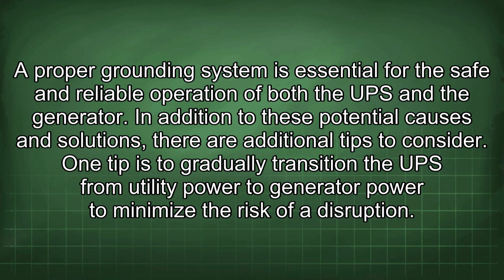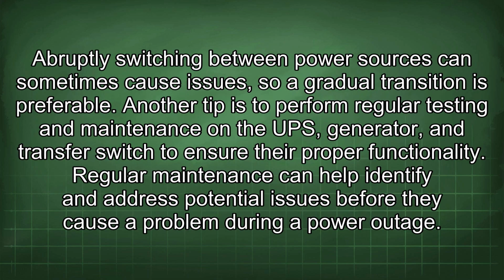In addition to these potential causes and solutions, there are additional tips to consider. One tip is to gradually transition the UPS from utility power to generator power to minimize the risk of a disruption. Abruptly switching between power sources can sometimes cause issues, so a gradual transition is preferable. Another tip is to perform regular testing and maintenance on the UPS, generator, and transfer switch to ensure their proper functionality. Regular maintenance can help identify and address potential issues before they cause a problem during a power outage.